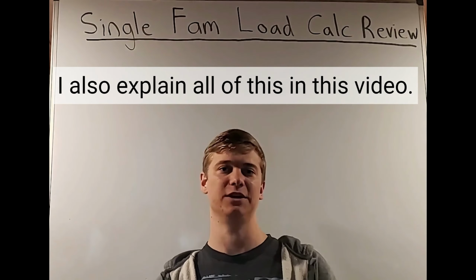And along with that, in the standard method, when you go to your duplexes and your multifamily, we're talking about dwellings here, then you're only going to do that 25% of the largest motor one time, no matter how many units you have. Again, that's explained in that part 2 video, and I'm also going to show you in these upcoming videos now that 25% of the largest motor. I'm going to have a duplex video and a multifamily video, so look out for those. Those are the videos right after this.